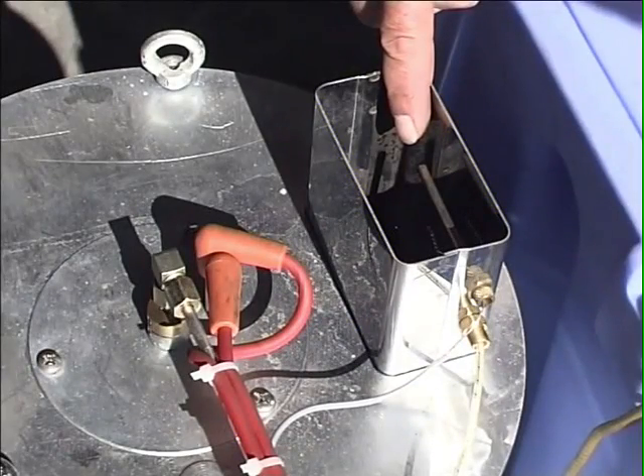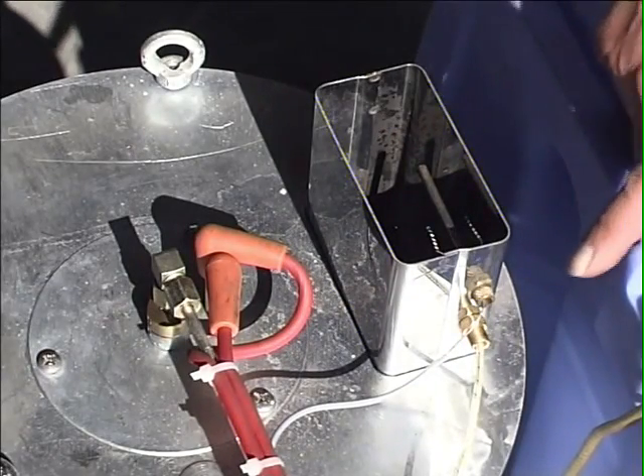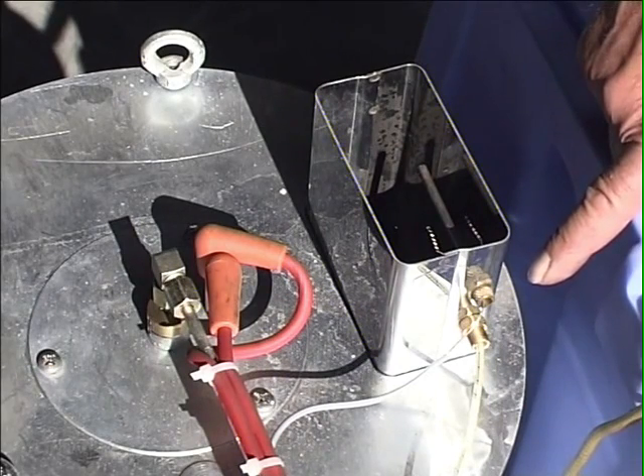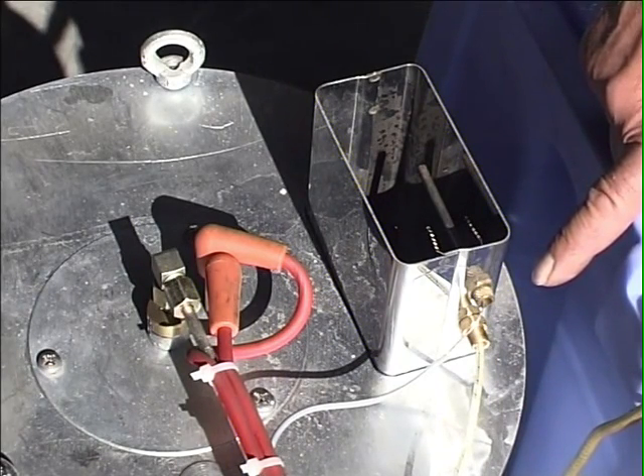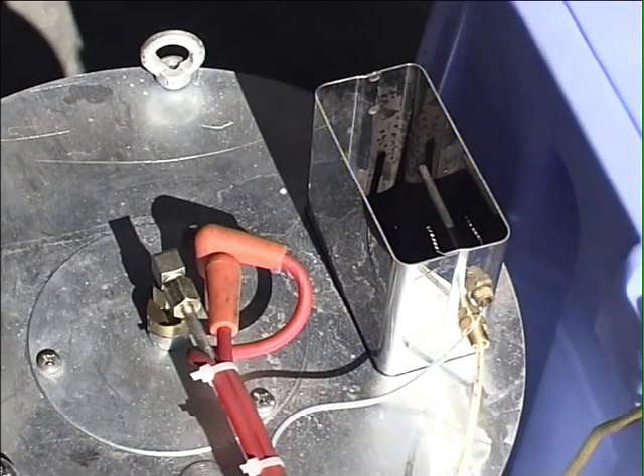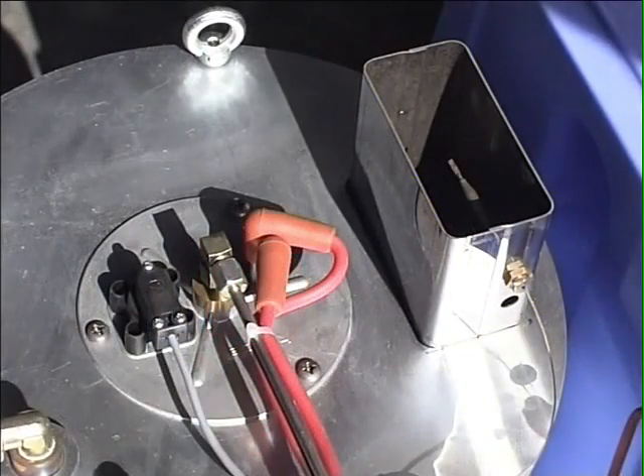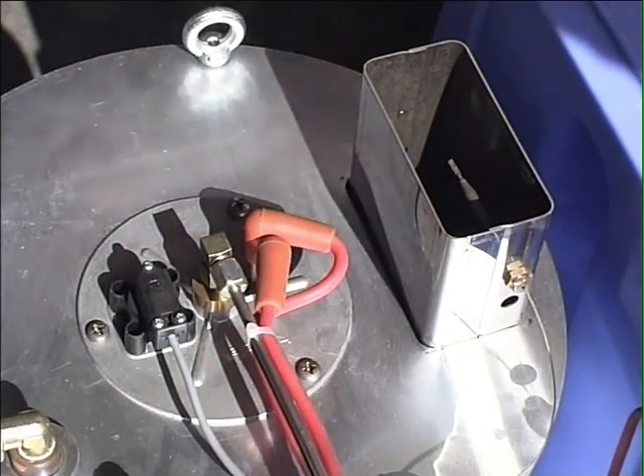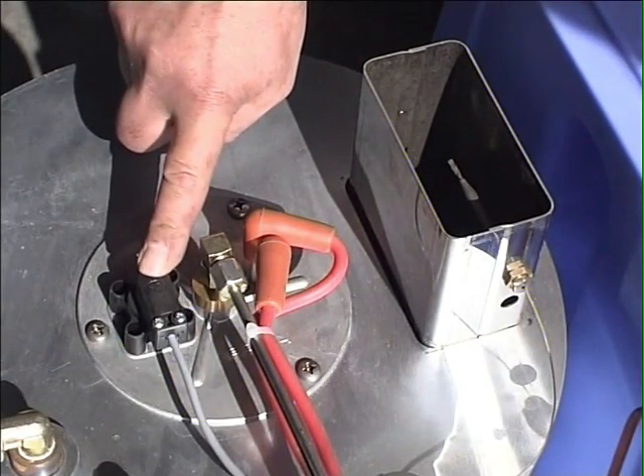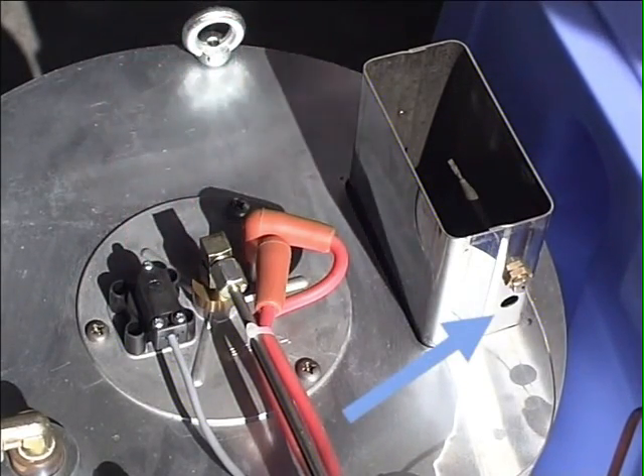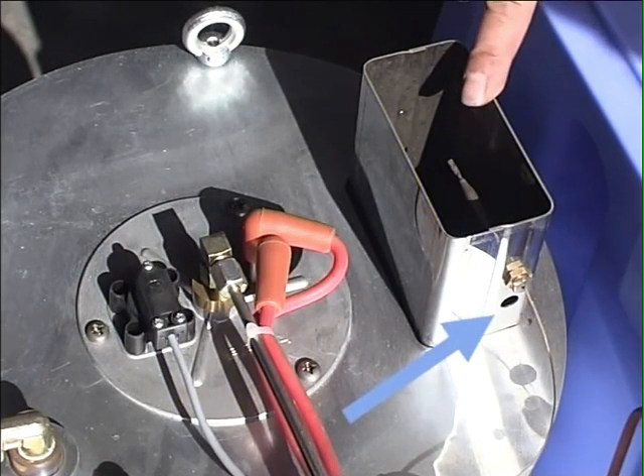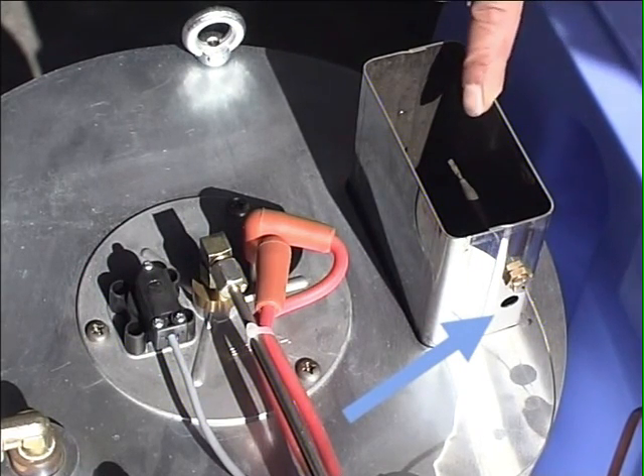Up to autumn 2003, the Therm was equipped with 2 probes in the chimney. The upper probe measured the waste gas excess temperature, and the lower the probe flame monitoring. If the temperature did not climb above 100 degrees Celsius in 14 seconds, oil supply was stopped. New models monitor the flame with a photocell. Thus, no longer a second probe in the chimney is necessary. Oil supply will stop immediately if no combustion takes place after 4 seconds.